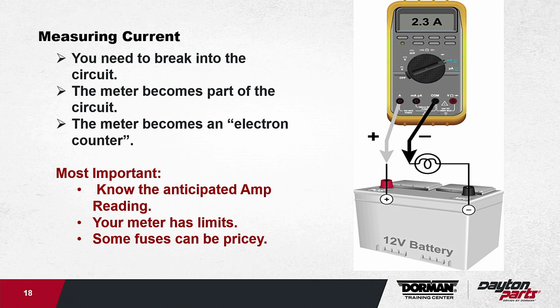So somebody might have told you, hey, you need to take an amp reading, and that's a perfect example where you can cause some issues. Whatever you do, you need to break into that circuit. If you don't, well, you can always use those inductive clamps, but breaking in gives a much more accurate reading. The meter becomes part of the circuit, okay, basically it becomes an electron counter.